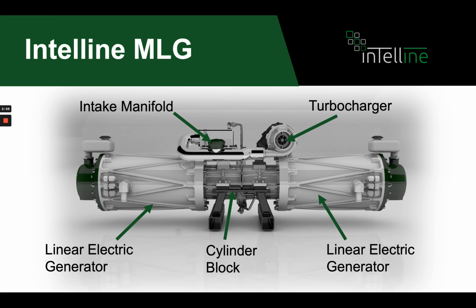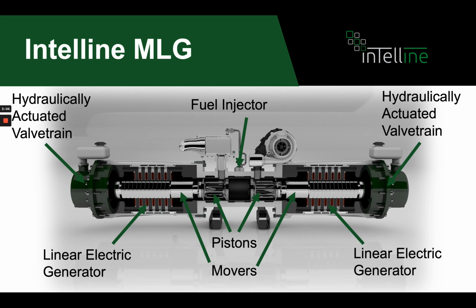The basic layout of the MLG involves a cylinder block in the center of the unit and two linear electric generators at each end. This engine does not rotate. The combustion in the center of the unit pushes the pistons apart, which bounce off of gas springs at each end of the unit. The mover shafts and pistons move back and forth in the unit, and the relative motion between mover and stator is how electricity is made.